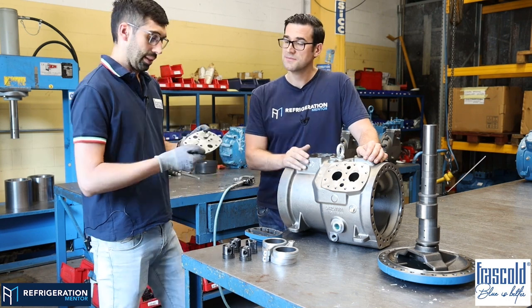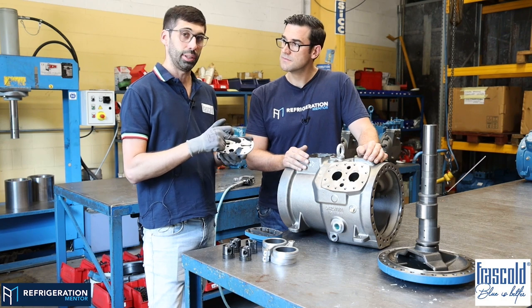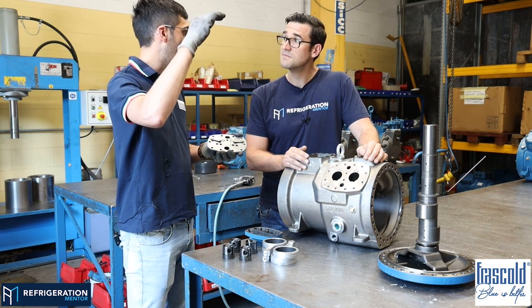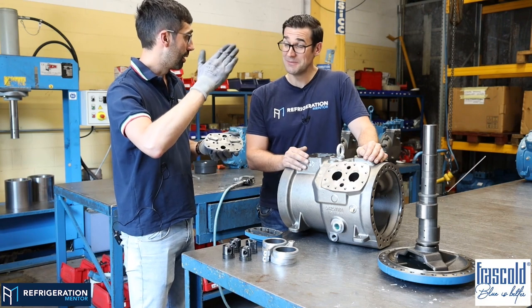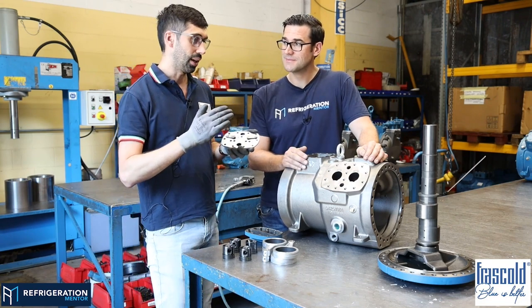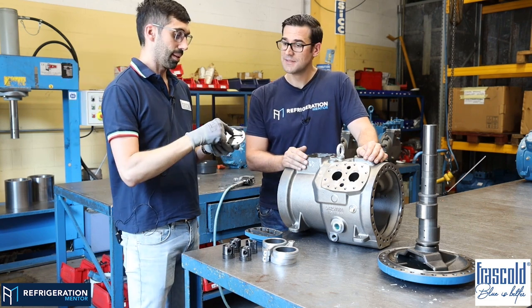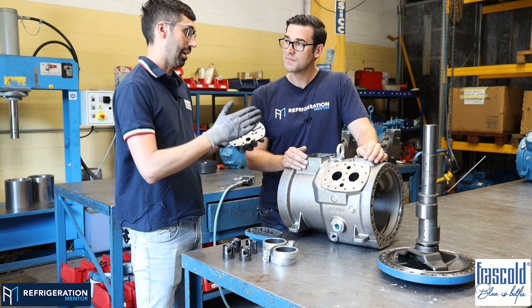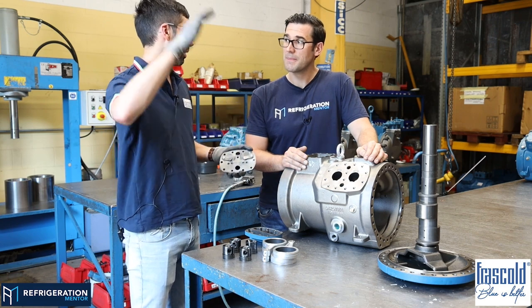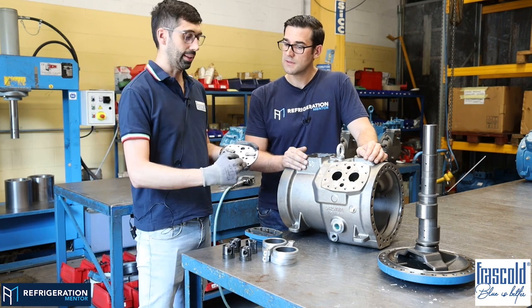What about the discharge ones? The discharge valve can break for many reasons. For example, thermal fatigue. If you reach uncontrolled high temperature and back to low temperature, maybe you have a liquid injection, but you didn't set up the timing. The PID control is not... You can face this diagram of temperature stressing the discharge valve, that is designed for thermal and mechanical stress, but not for very big thermal stress. So this is just one example. What happens? It can break like this.